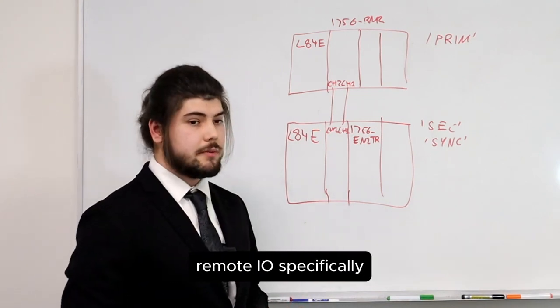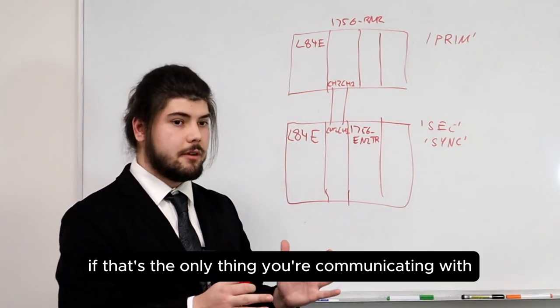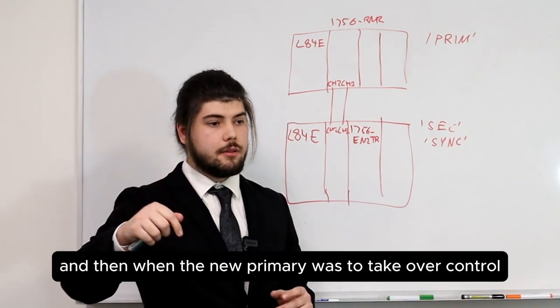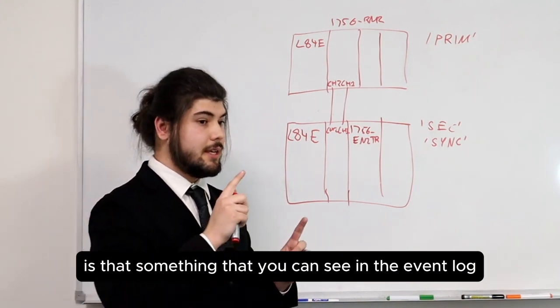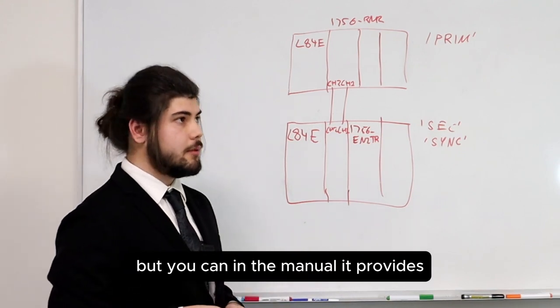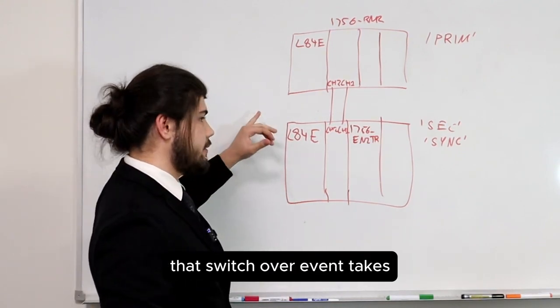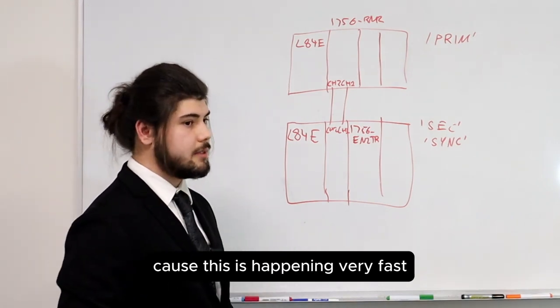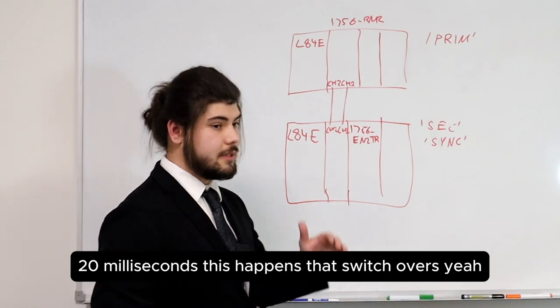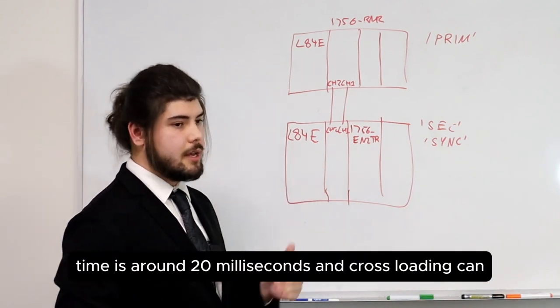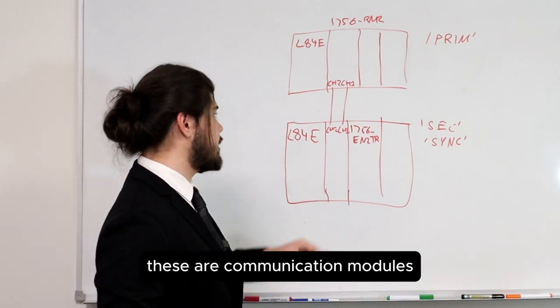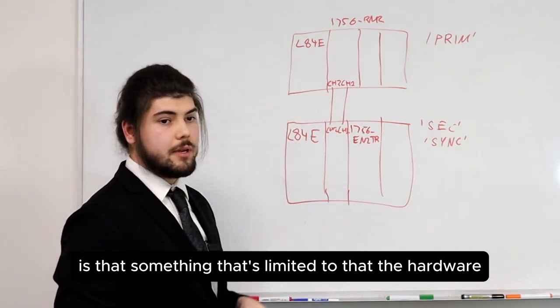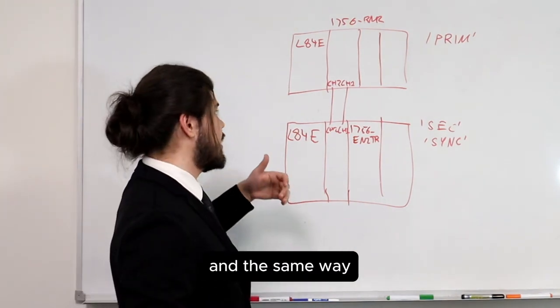IP swapping is a consideration specifically for remote IO — you don't need it for HMIs, for example. In the event log, everything is timestamped, so you can see when the switchover event occurred and when the new primary takes over control. The manual provides substantial documentation of how long that switchover takes. With Ethernet modules, communication can be lost momentarily during switchover — that loss of communication would be no longer than 20 milliseconds. The switchover time is around 20 milliseconds, and cross-loading can occur extremely fast as these communication modules communicate at 1,000 megabits per second. The switchover occurs automatically and is limited to the hardware and firmware.